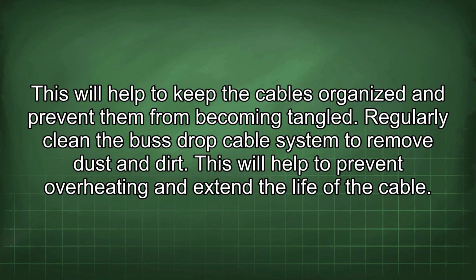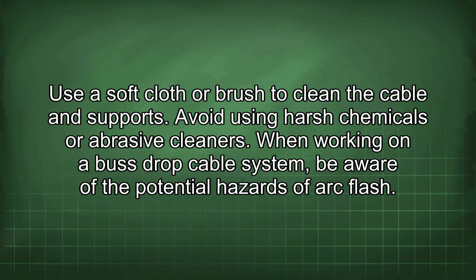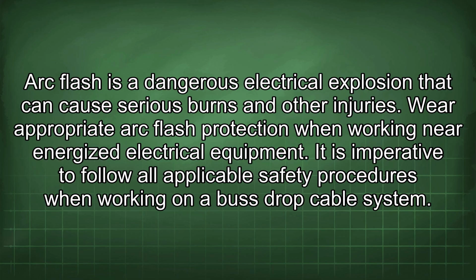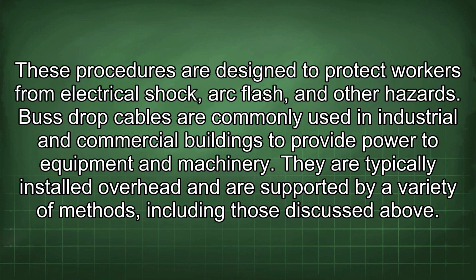Regularly clean the bus drop cable system to remove dust and dirt. This will help to prevent overheating and extend the life of the cable. Use a soft cloth or brush to clean the cable and supports. Avoid using harsh chemicals or abrasive cleaners. When working on a bus drop cable system, be aware of the potential hazards of arc flash. Arc flash is a dangerous electrical explosion that can cause serious burns and other injuries. Wear appropriate arc flash protection when working near energized electrical equipment. It is imperative to follow all applicable safety procedures when working on a bus drop cable system. These procedures are designed to protect workers from electrical shock, arc flash, and other hazards.